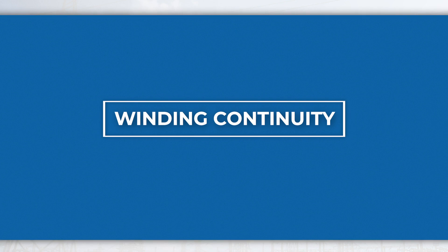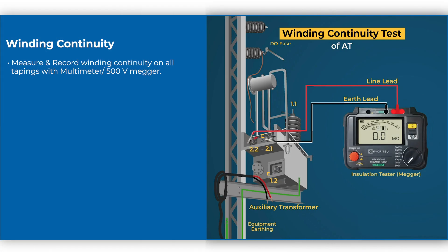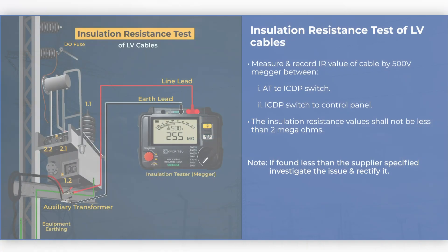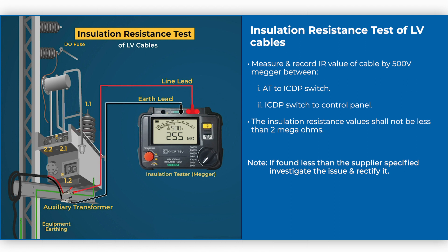Winding continuity: Measure and record winding continuity on all tapings with a multimeter or 500 volt megger. For insulation resistance test of LV cables, measure and record IR value of cable by 500 volt megger between AT to ICDP switch and ICDP switch to control panel. The insulation resistance values shall not be less than 2 mega ohms. If found less than the supplier specified value, investigate the issue and rectify it.